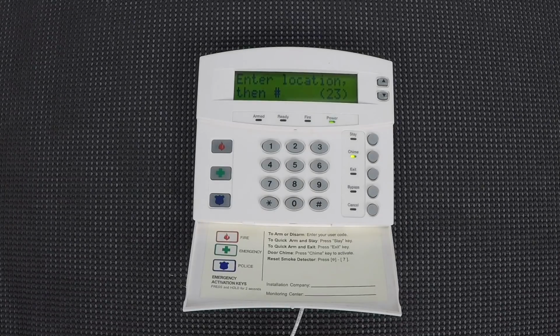You can do that just by going to that zone type, which is zone type 3. There's a location that corresponds to it, and you can turn that option on. So, that's the example we're going to do for this. You'll want to refer to the manual for your panel for all the different zone types. We don't have them fully listed out, but basically it's going to be within locations 111 to 169 for most of the panels.